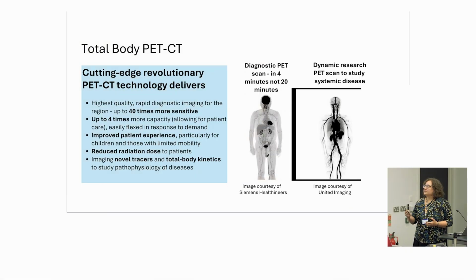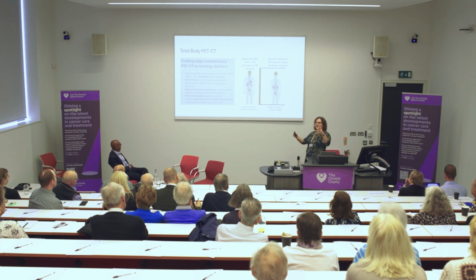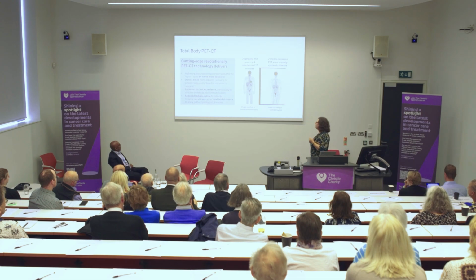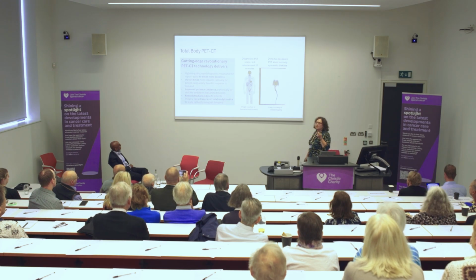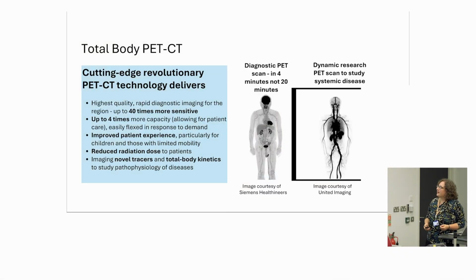The real world advantage of this is twofold. One is that conventional patient imaging can be done really quickly. The detector is 40 times more sensitive. It might be 4 or 5 times longer, but the actual detector, because it's covering more of the patient, picking up more of the signal in one go, is 40 times more sensitive. And because we can scan so much faster, we can release up to 4 times more capacity. And because we've got more capacity to scan patients, it also means that if we have a problem with a scanner elsewhere in the region, we can bring more capacity onto the Christie site and be more resilient in making sure patients are not waiting longer for their scans.